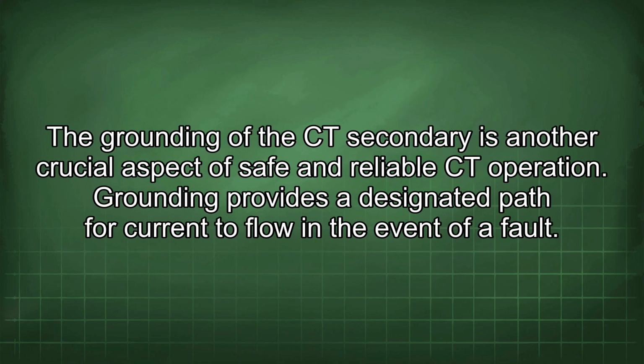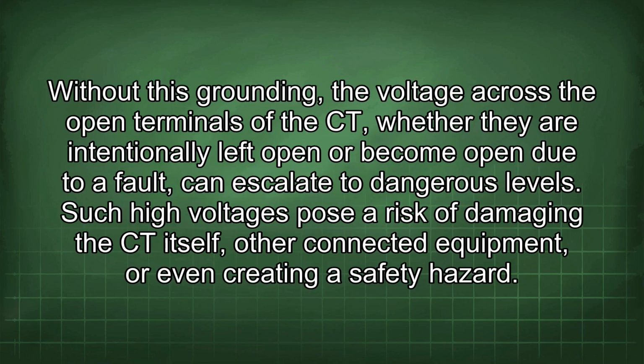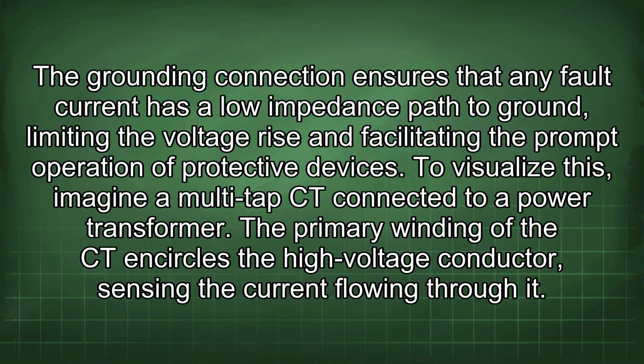The grounding of the CT secondary is another crucial aspect of safe and reliable CT operation. Grounding provides a designated path for current to flow in the event of a fault. Without this grounding, the voltage across the open terminals of the CT, whether they are intentionally left open or become open due to a fault, can escalate to dangerous levels. Such high voltages pose a risk of damaging the CT itself, other connected equipment, or even creating a safety hazard. The grounding connection ensures that any fault current has a low impedance path to ground, limiting the voltage rise and facilitating the prompt operation of protective devices.